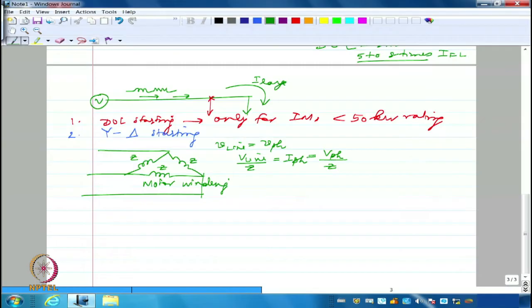Right? Whereas, if I try to look at line currents, what is drawn from the supply, what the motor is drawing is different, what is actually drawn from the power supply is √3 times that motor phase current. And so power system authorities are going to look at only this √3 times the phase current, right? So, I am going to have this I line to be √3 times V phase divided by Z, right? Rather than this, if I try to make initially the winding get connected in star, I don't want it in delta, I want the same thing in star, right? So I will still have the impedance to be Z, Z and Z. Nothing has changed. The same winding I am reconnecting in star, right?